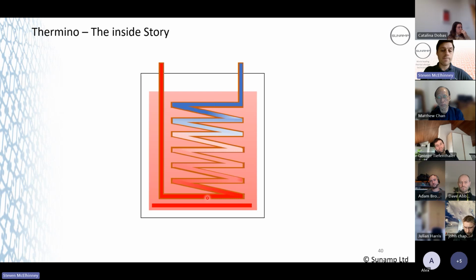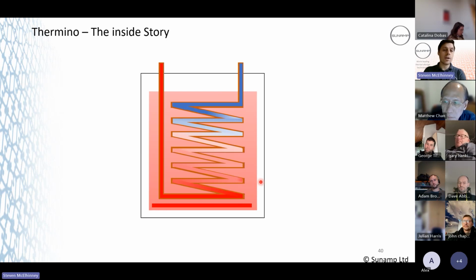So the reason for that is it's all to do with the set points, and I'll explain that a little bit later. It's so the unit can, if you're discharging from the bottom, that bottom sensor recognises there's a massive drop in temperature straight away. So what the unit does, it recognises that, and then it makes itself available for solar. So the set point's a lot higher. So a Thermino E, if you discharge 20% of your capacity, it then generates a demand. With an ePV, if you discharge 5% of your capacity, it then generates a demand. So that's the reasoning for that there.